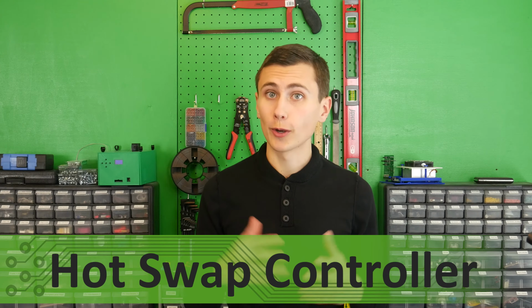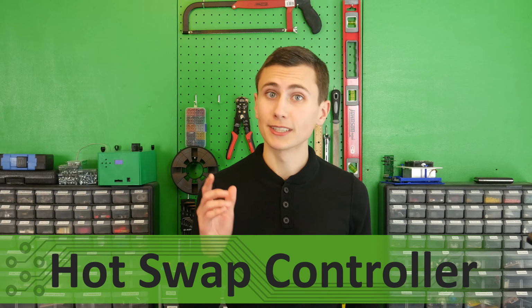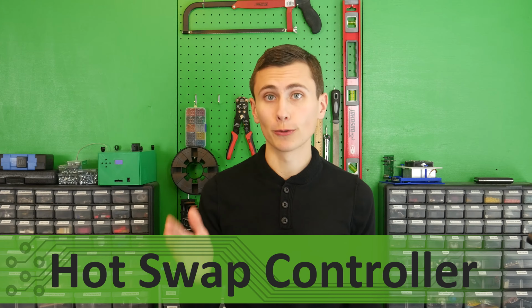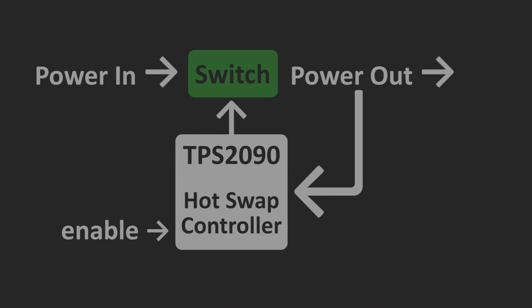Today we're going to talk about a component that limits inrush current but still allows massive quantities of power to flow. At least that's the theory. We implemented what is called a hot swap controller in our UPS. This device drives some N-channel FETs to slowly turn on a downstream DC load, and this hot swap controller continuously monitors the power delivered, and it serves as an electronic circuit breaker in case of a fault. We use this circuit for both its main function and some extra ones in our UPS project, and we're about to walk through exactly what our experience was while designing and testing this circuit.